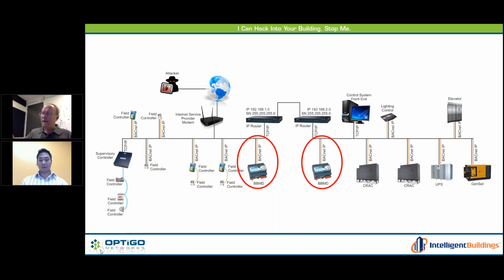IT has two routers sitting there, and they're on different subnets or different network address areas. Well, the BBMD just punched a hole through that, so all those firewall rules and everything are gone. Now the bad guy can hit this BBMD, and - I'm going to show you a bit of the tool and what it can do - they can jump over to the generator, and if they want to, run it dry. They can raise all the set points on the data center floor, and then you start having servers trip off. That's the kind of outlay of where we're at now.